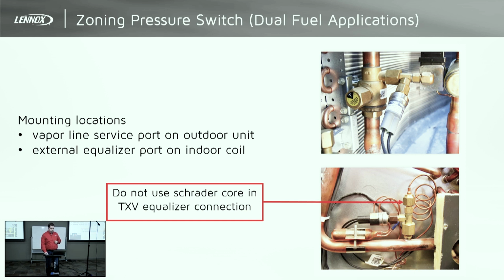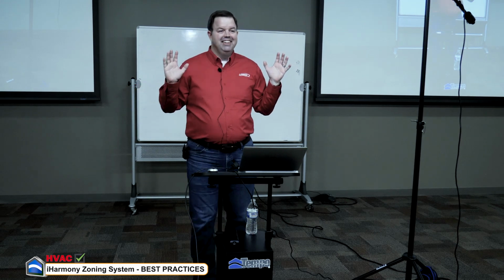And since your equalizer line on your TXV doesn't have a Schrader depressor in it, it doesn't get your evaporator pressure. And your TXV doesn't work. And I can promise you that if you install one of these and then you replace the evaporator coil and then you change the TXV and then you change the TXV again and then you call me because it's a piece of junk and your homeowner's angry, I will step out away from the bus so that it runs you over. Because at that point I can't help you out. You gotta pay attention to that.